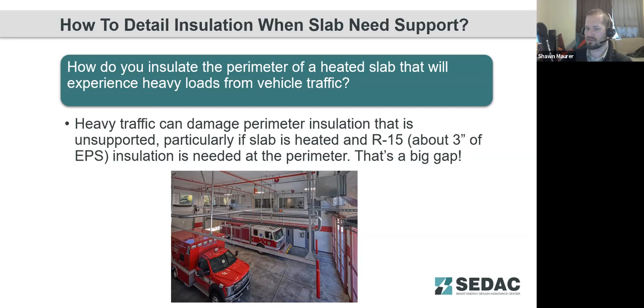But you do have this concern where now that slab is heated to provide that radiant energy into the space, you've got to insulate under the slab and then wrap it up on the edges. And per the energy code, that can be anywhere from 2 to 3 inches of EPS insulation that leaves a gap between your exterior driveway slab, loading dock ramp, whatever it happens to be, and the interior heated slab. And so how do you address that gap and provide structural support so that the edge of the slab doesn't break down over time and the insulation itself isn't impacted and crushed by traffic moving over that material?